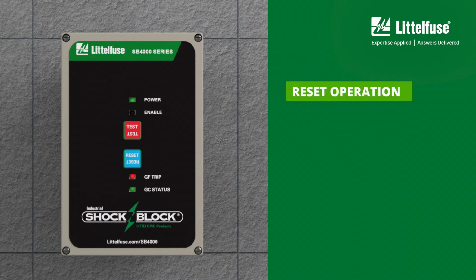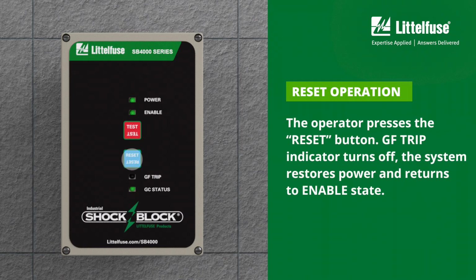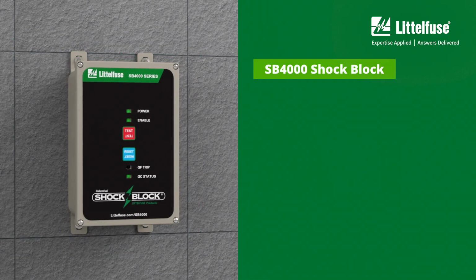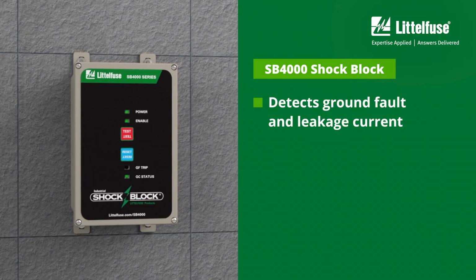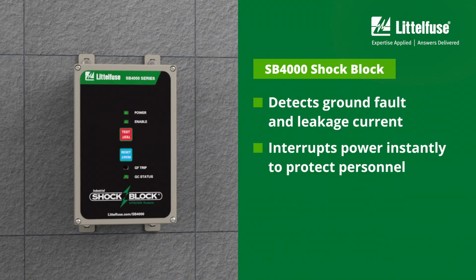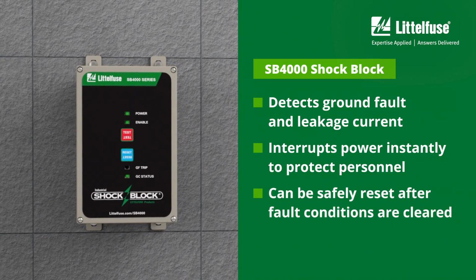Reset operation. The operator presses the reset button. GF trip indicator turns off, the system restores power and returns to enable state. The commissioning is now complete. The SB4000 detects ground fault and leakage current, interrupts power instantly to protect personnel, and can be safely reset after fault conditions are cleared.